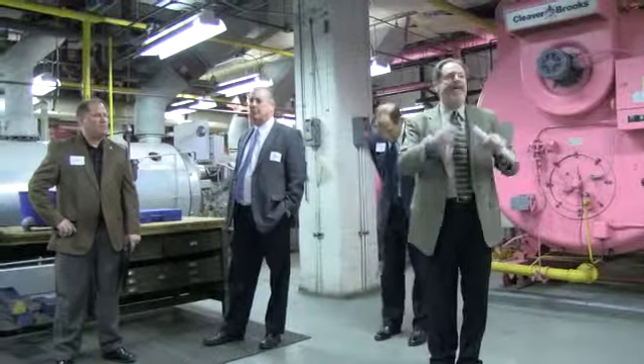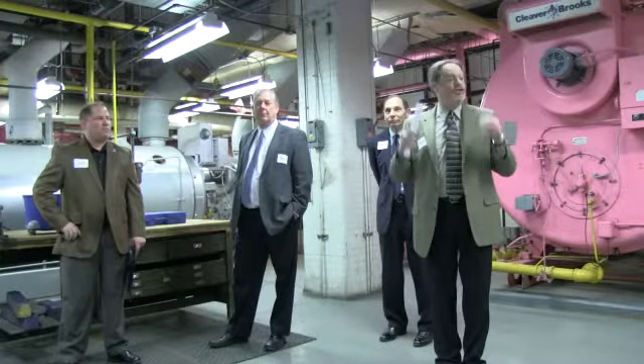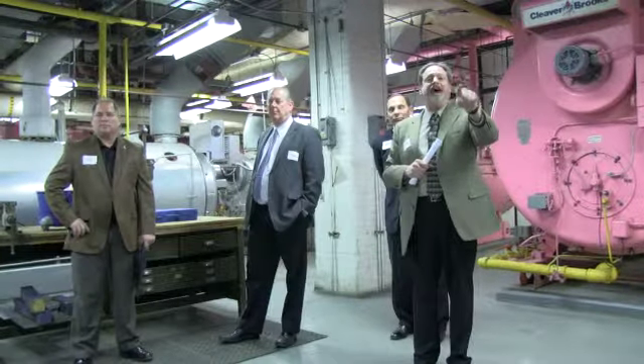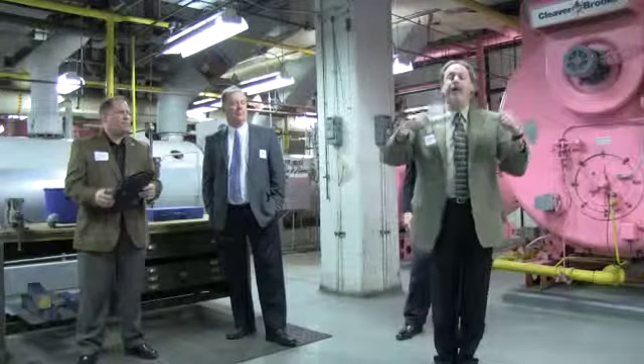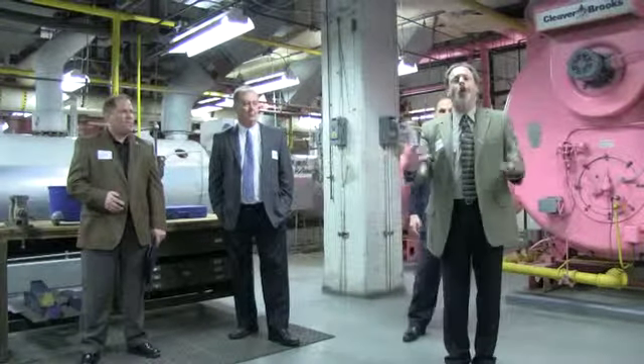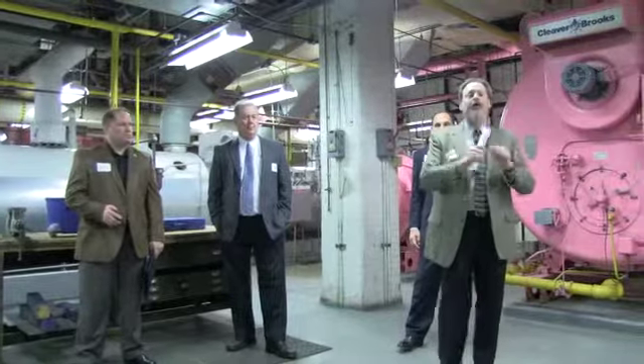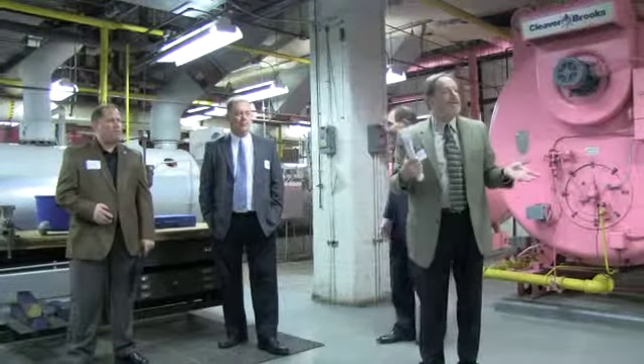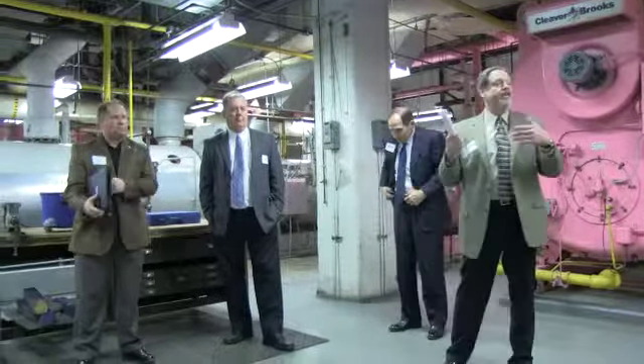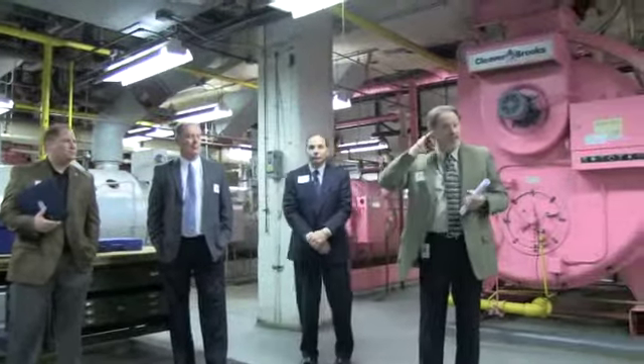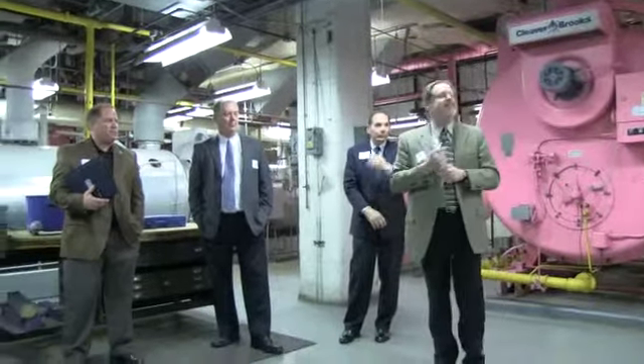So what we do to try to keep utility costs down is we produce ice after hours at nighttime when the sun's down and the utility rates are a little bit better and the utility company gives us a break on our utility costs to use electric at night to produce ice. We get those tanks filled with ice, then we pipe through another series of coils that are going through that. We pipe water through there. We take that water and make it colder by taking that ice temperature and cooling that water, and then we send it out to the building for cooling purposes. So it's a unique way, it's kind of the green way of using a piece of equipment to give you, I guess, a better way to operate your system. That was not put in recently, that was put in 1990, so that's been here for a lot of years. It's been a really good savior for us to keep our utility costs down.